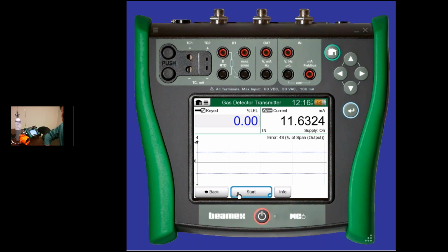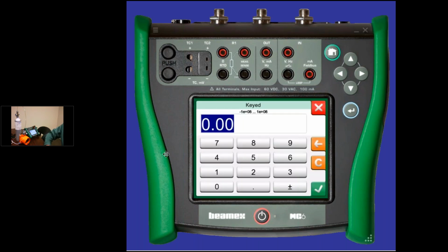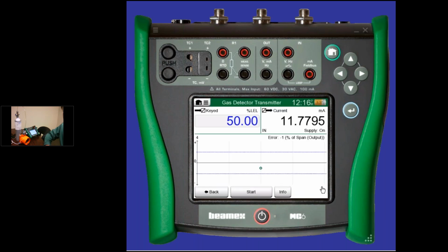Let's see, I'm going to key in that my LEL is 50%, so I'm just in a troubleshooting mode here. There we go. And we're getting back up about where we were before at 11.8 milliamps. So I need to run the milliamps up. So let's see if we put the magnet here. There, I made it jump too much. And I made it go back down. So that's pretty good. I'm sitting here at 50, and I'm getting about 12.04. So that looks real good.